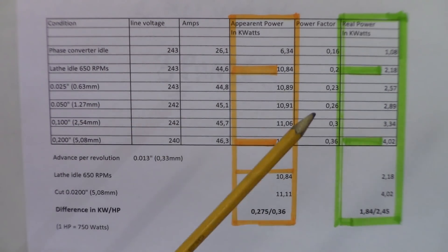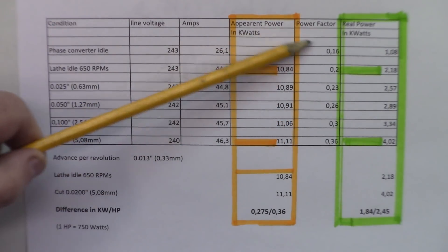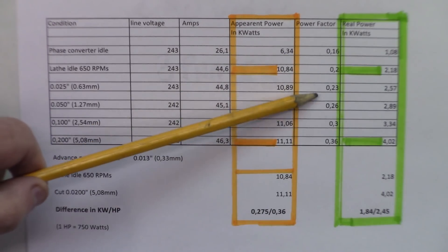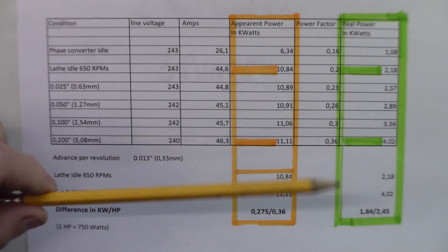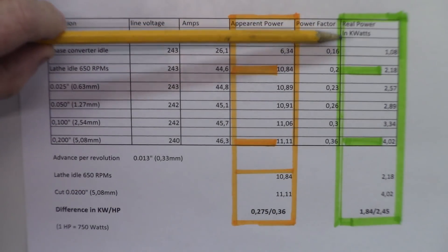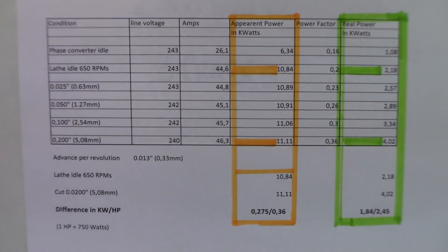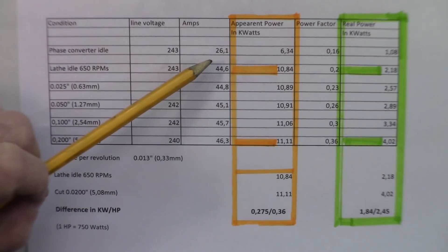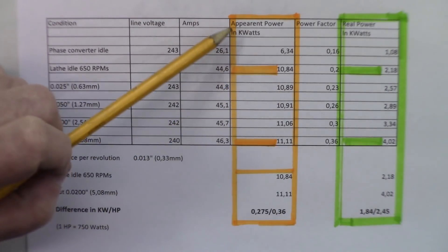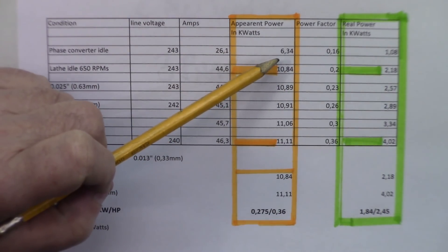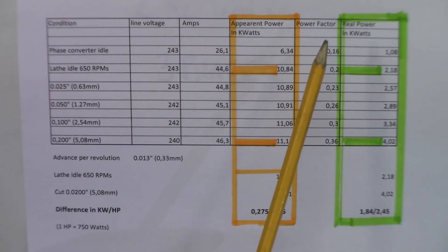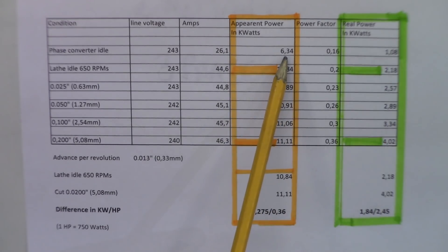That's where the power monitor comes into play. That's going to give you a power factor here of the different conditions according to the different phase shifting into the system. So this will give you, in the last column there, the real power drawn in every condition. So what I did here, let's say you're taking the phase converter idling, it's 243 volts multiplied by 26 amps, it's going to give you an apparent 6.34 kilowatts. This is a lot of power, but if you get the conversion with the power factor of 0.16, you will get, in fact, a real power consumption of 1.08, almost 1.1 kilowatt. So this is quite less than this figure here.